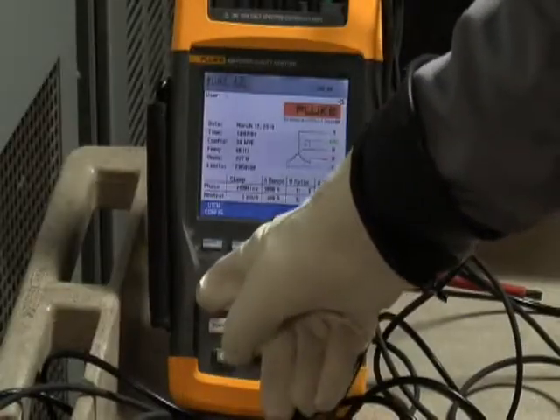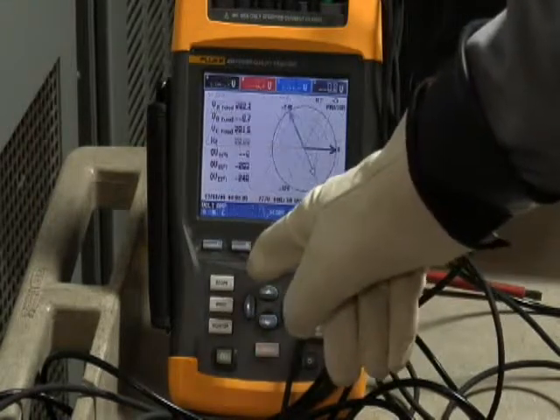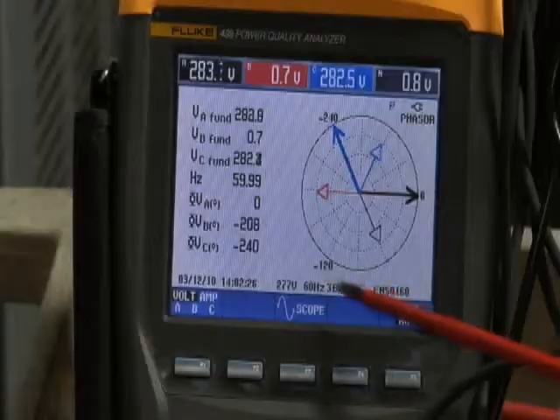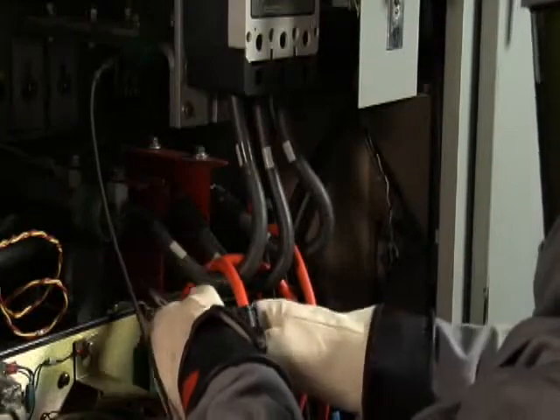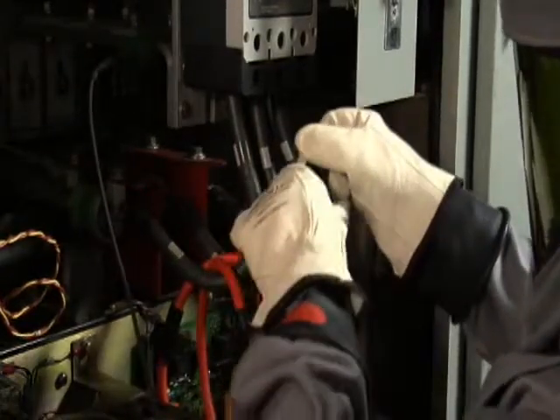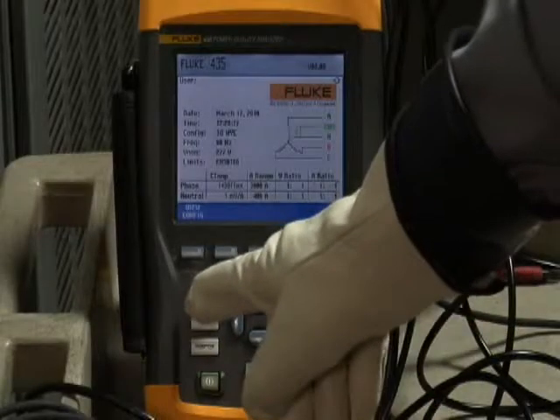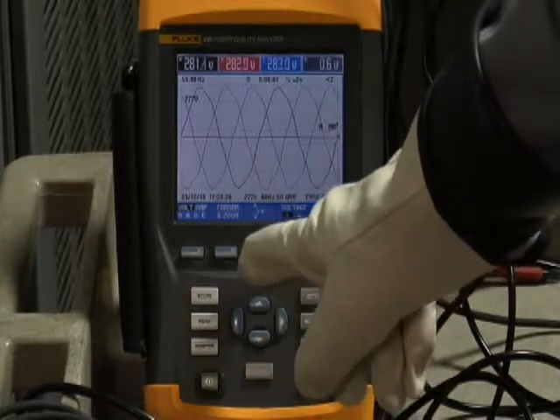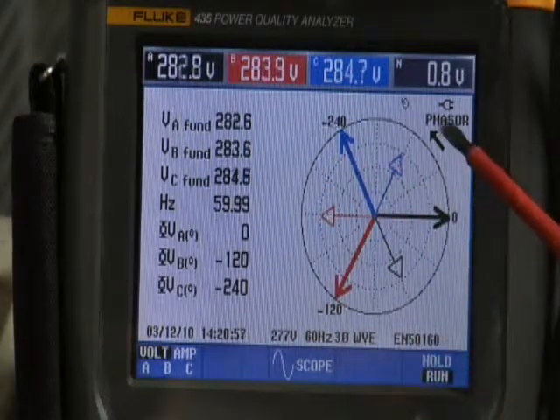Missing voltage. Another common problem is having one of those voltage leads pop off long after you've left the equipment. You'll see this indicated on the power quality analyzer — on the scope screen, you'll notice that one of the phases is missing, and the same is true on the phasor diagram. To correct this, go back into the equipment and securely fasten that voltage lead. Then go back to your power quality analyzer, make sure all three phases are present, and check the phasor diagram to confirm it is correct.